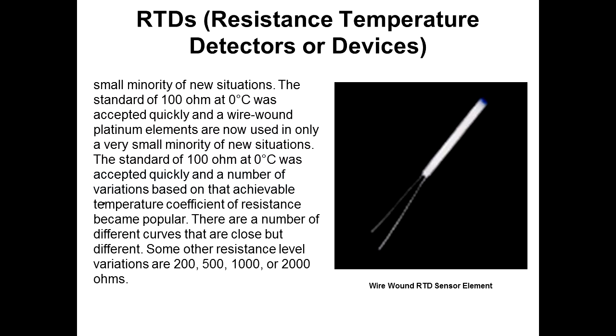The standard 100 ohms at 0 C was accepted quickly, and wire-wound platinum elements were now used only for specialized applications, mainly for things like laboratory use, where they can be made to be more accurate than a thin film sensor, but they're also much more fragile in those configurations. There are other popular resistance levels out there other than the 100. There's 200, 500, 1,000, and 2,000 ohm units. But when you start getting up into the high end here, you have self-heating issues, so you've got to compensate for that.